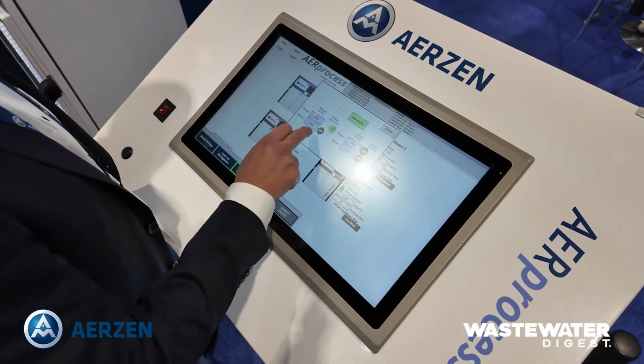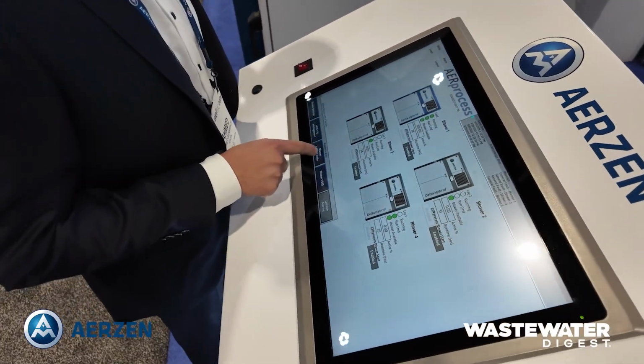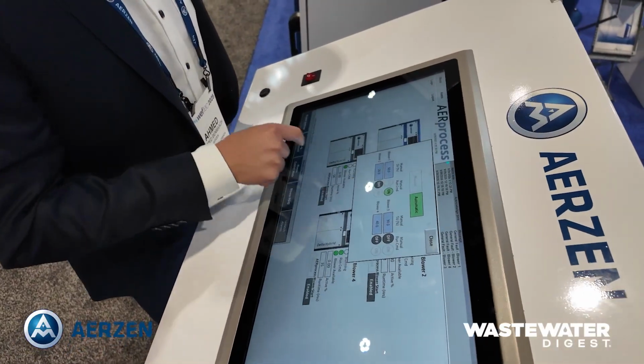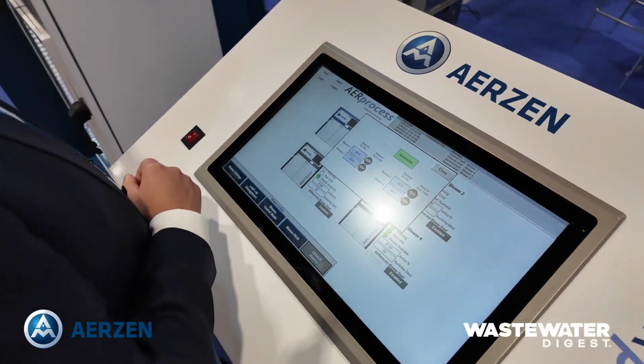The rest of it is in how the rate of change in the system gets managed. Over the course of a day or a week, you'll have different demands, whether it's a change in flow or a change in the strength of the waste coming in, or even seasonal changes like temperature. The traditional way of controlling the rate of change was what they called PID loops, and that is really geared around systems that have linear responses. And a wastewater treatment plant is anything but linear, for those reasons I just said.